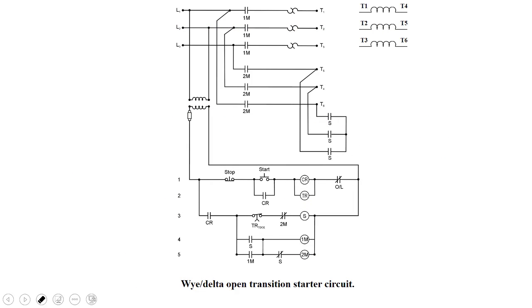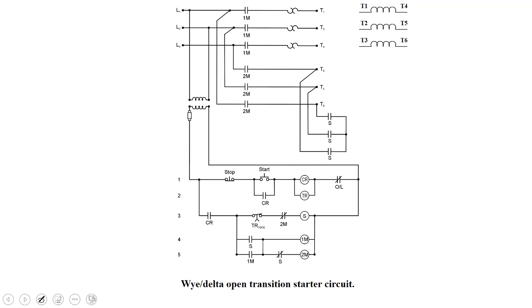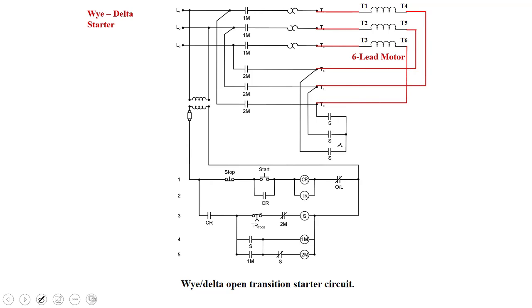So here's a Y delta open transition starter. Let's go ahead and follow this through. If you notice, we've got 3 sets of power contacts. These are our star right there. They make the star when I energize the 1M. I better wire this up. So there we go. T1 goes to 1, T2 goes to 2, 3 to 3, and then 4, 5, and 6 come back. And that's how we'd have 6 leads going out to the motor from our starter.